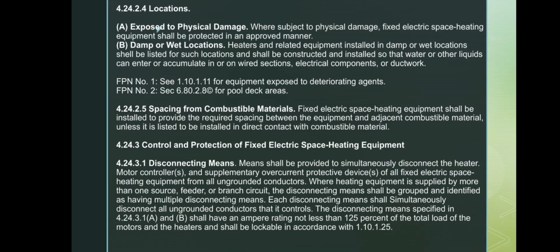Next, the slide covers the installation rules for fixed electric space heating equipment. First, under section 4.24.2.4, locations. Exposed to physical damage: if the heater is placed where it can be physically damaged, it must be protected using approved methods. B. Damp or wet location: any heater installed in damp or wet areas must be listed for those locations and built so water cannot enter wiring, electrical parts, or ductwork. There are two notes. One refers to equipment exposed to deteriorating agents, and the other applies to pool deck areas.